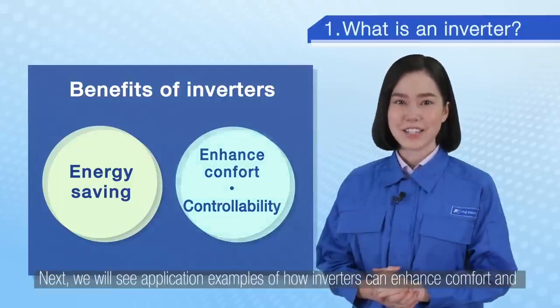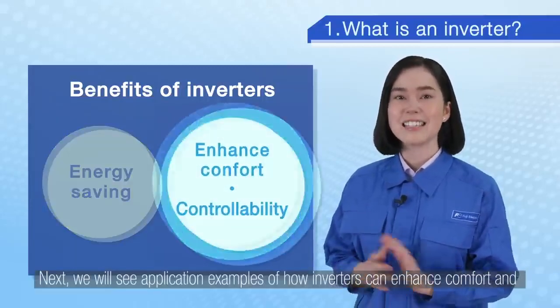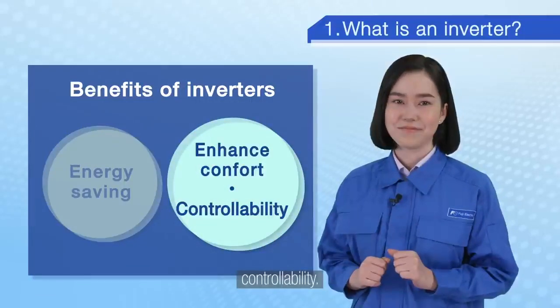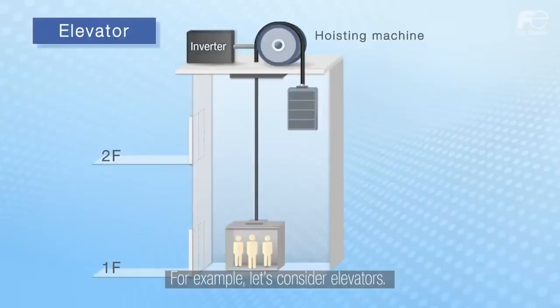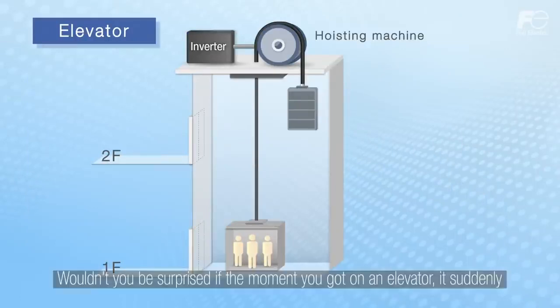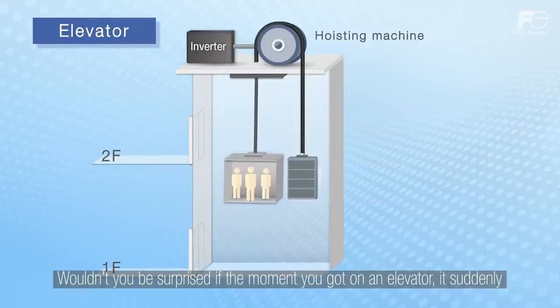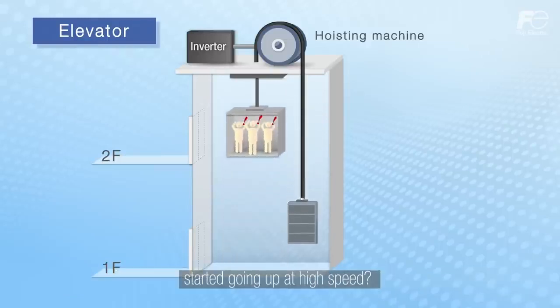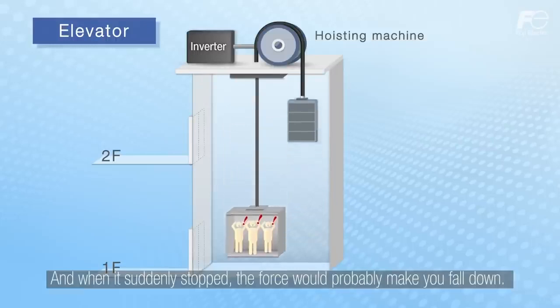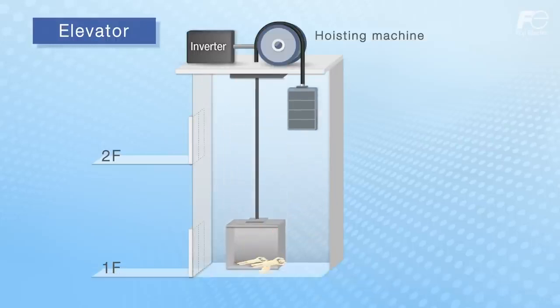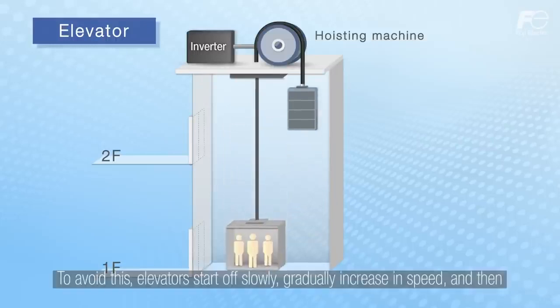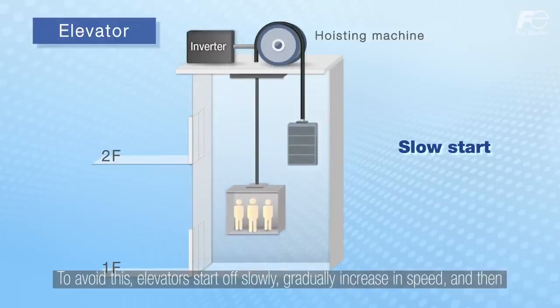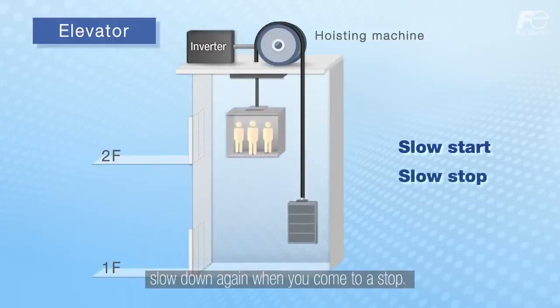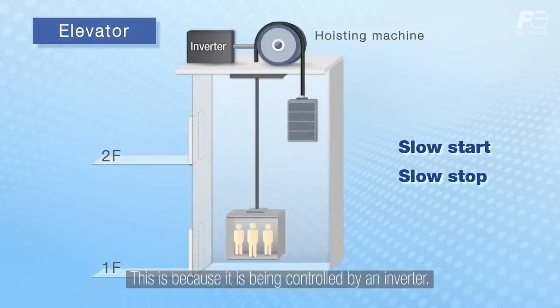Next, we will see application examples of how inverters can enhance comfort and controllability. For example, let's consider elevators. I assume that everyone has ridden in an elevator. Wouldn't you be surprised if the moment you got on an elevator, it suddenly started going up at high speed, and when it suddenly stopped, the force would probably make you fall down? To avoid this, elevators start off slowly, gradually increase in speed, and then slow down again when you come to a stop. This is because it is being controlled by an inverter.